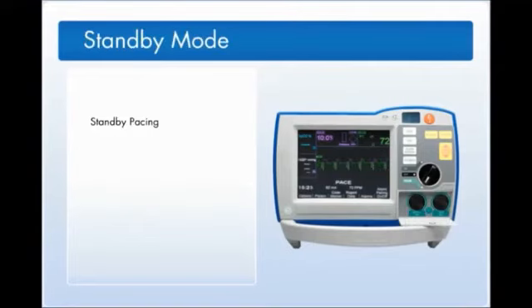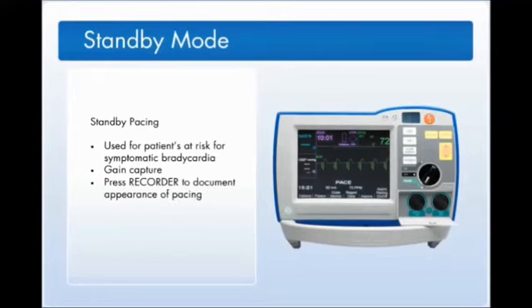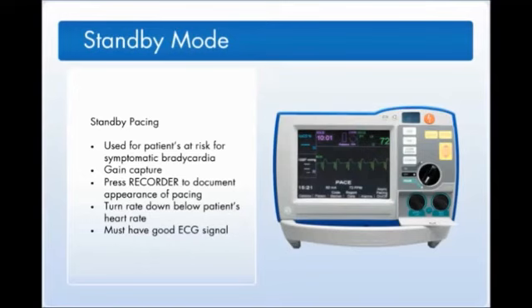When a patient is at risk of developing symptomatic bradycardia, you can use the pacer standby mode. To do this, gain capture, then press Recorder to document the appearance of pacing for this patient. Next, turn the rate down to below your patient's heart rate. Because this is a ventricular demand pacer, the pacer will only be active when the patient's heart rate falls below the set rate. Make sure that you have a good ECG signal when using standby pacing.